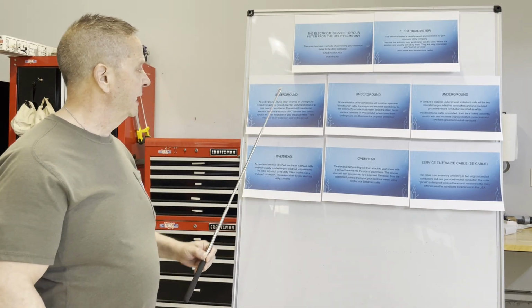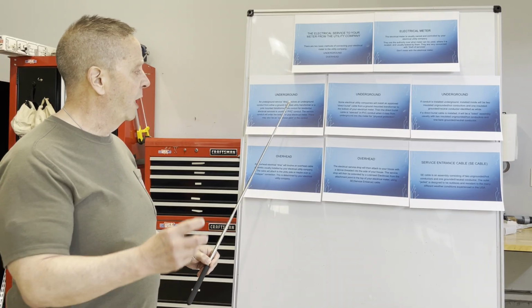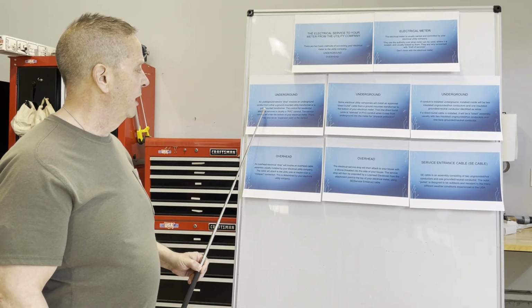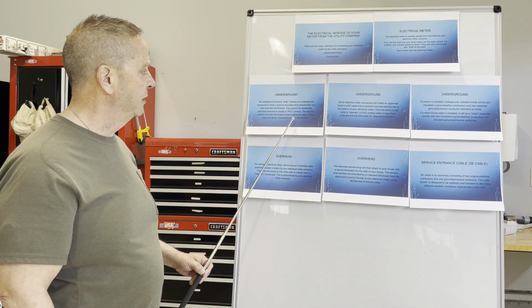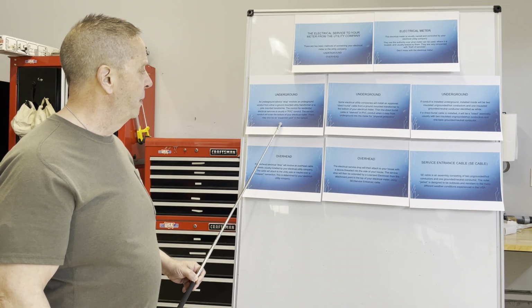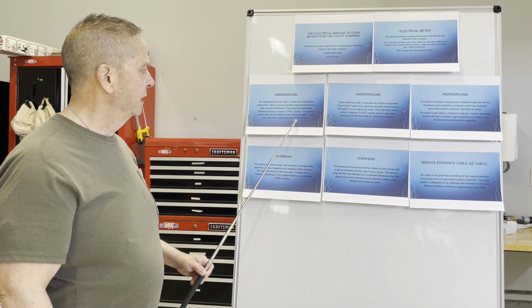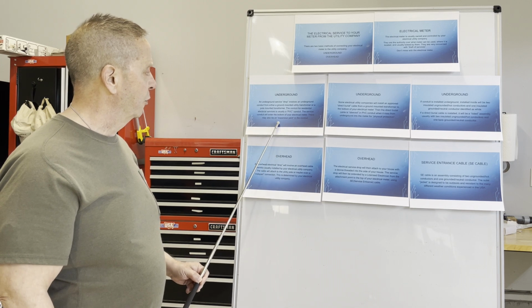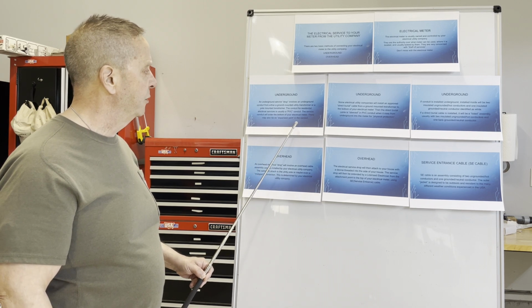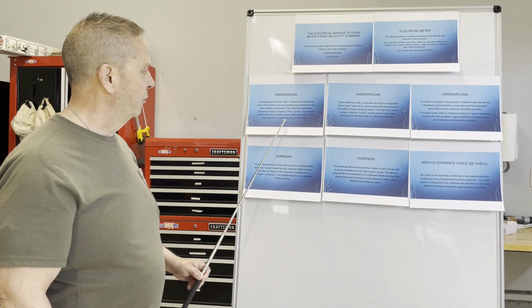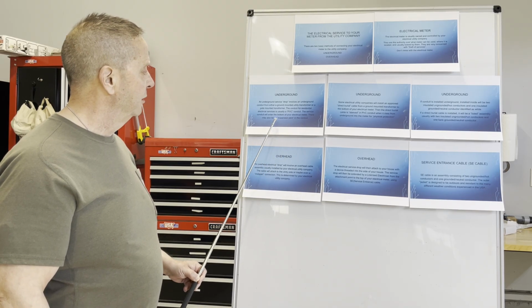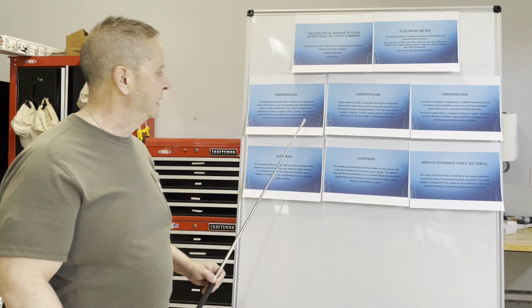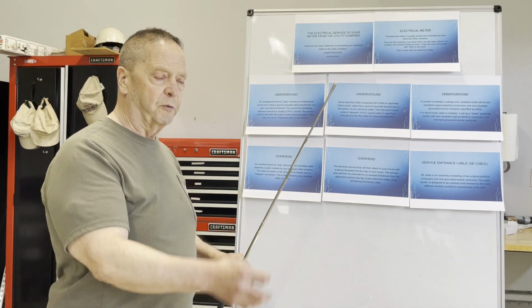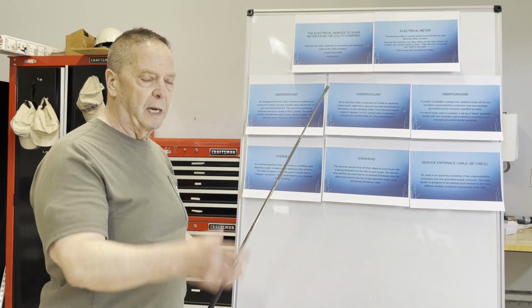If you have an underground service, the drop involves an underground conduit from either a ground-mounted utility transformer or a pole-mounted utility transformer. The conduit for residential electrical services is usually PVC conduit. The service conduit will enter the bottom of your electrical meter.